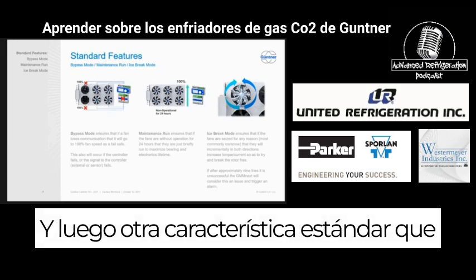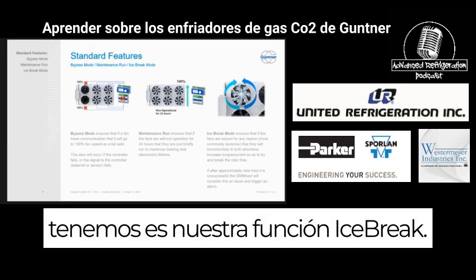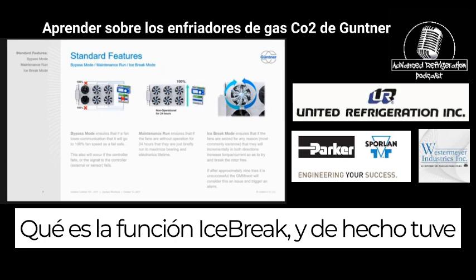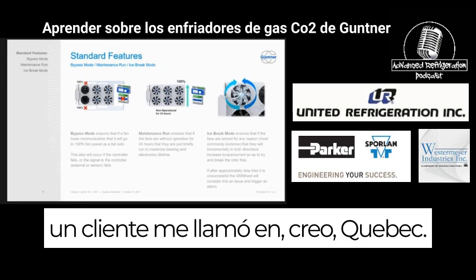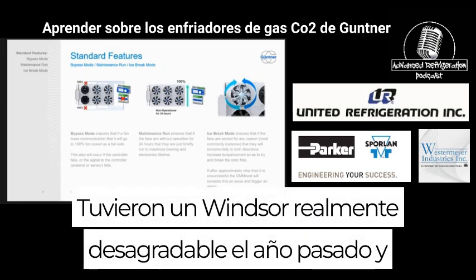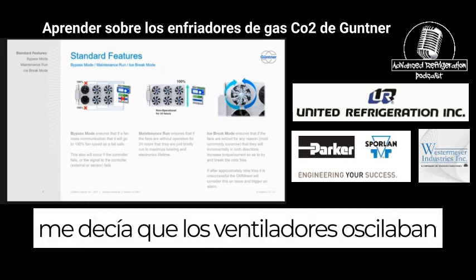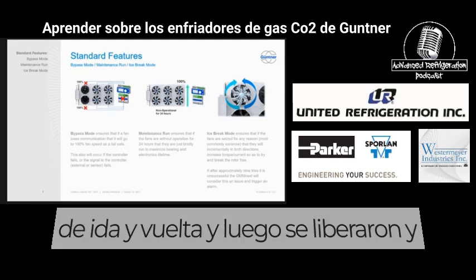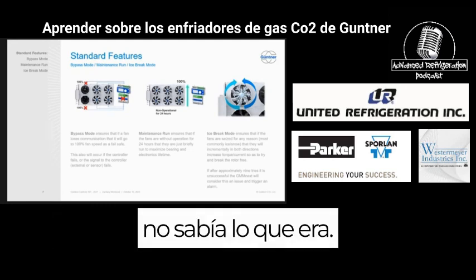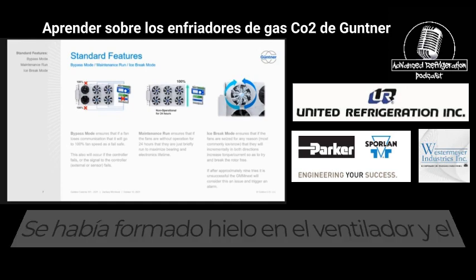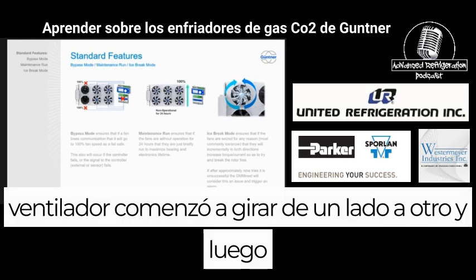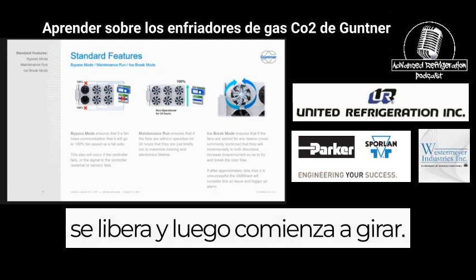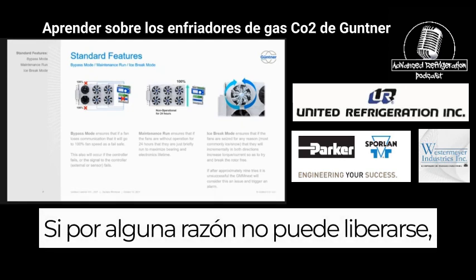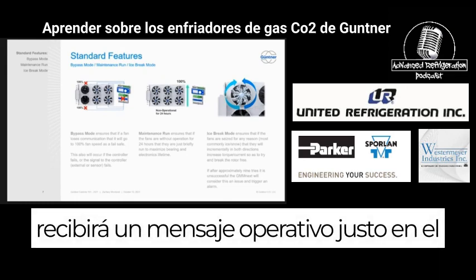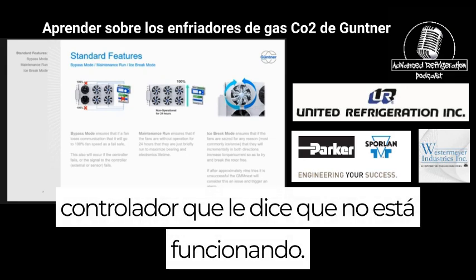And then another standard feature that we have is our ice break feature. I actually had a customer call me up in, I think, Quebec. They had a really nasty winter last year. And he was telling me that the fans were oscillating back and forth and then they broke free, and he didn't know what it was. It was because ice had formed on the fan, and the fan started spinning back and forth and then broke free and started spinning. If for whatever reason it can't break free, you'll get an operational message right on the controller telling you that it's not working.